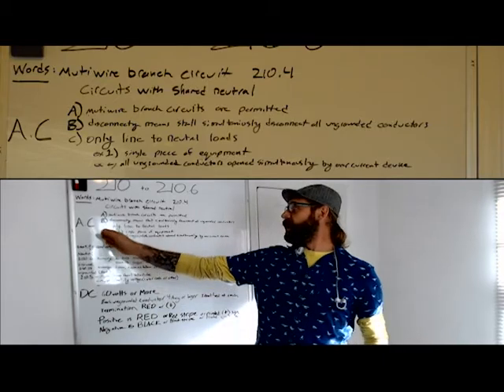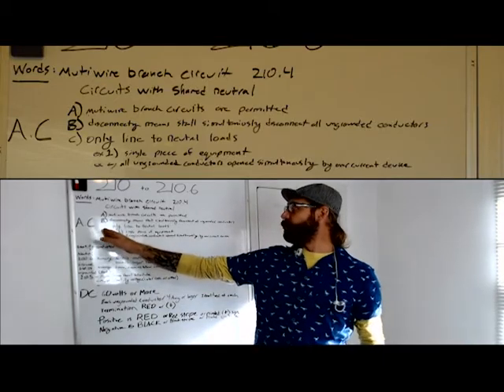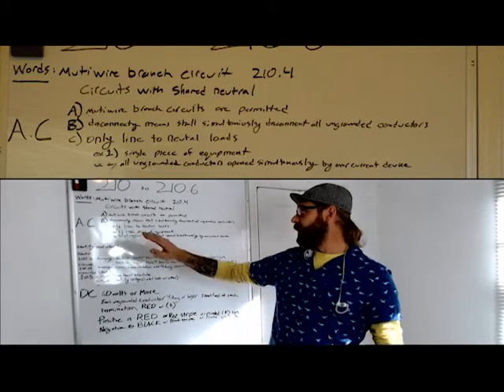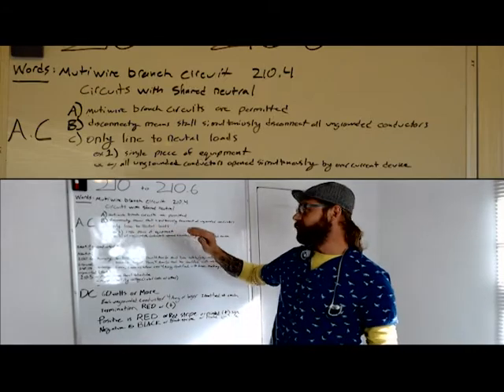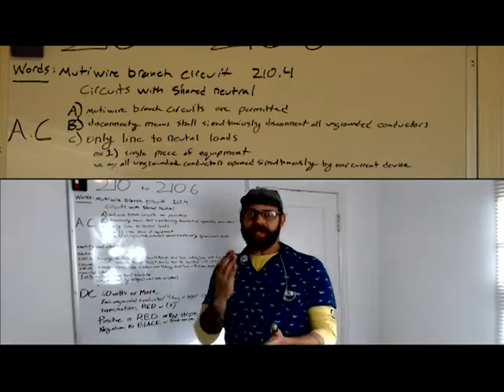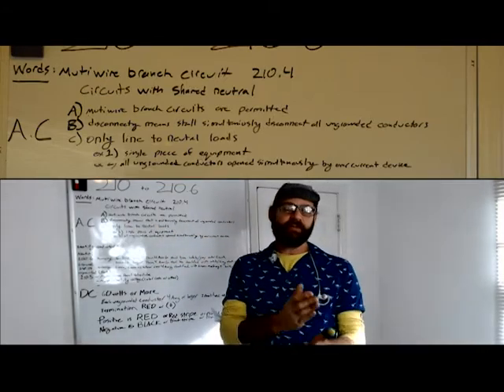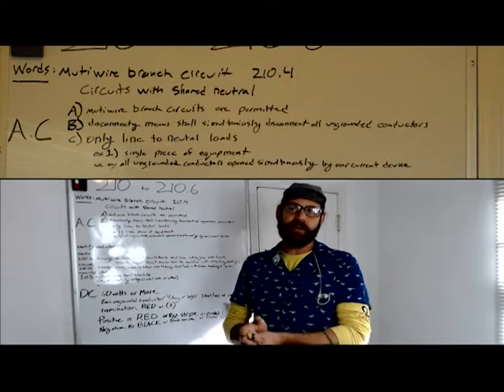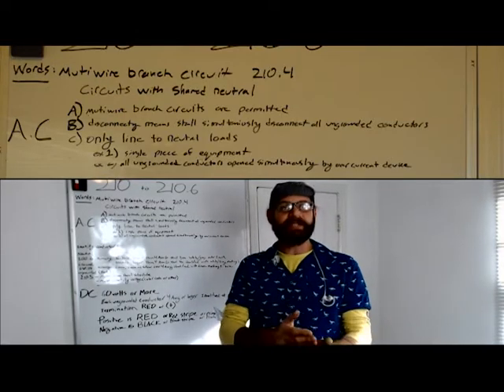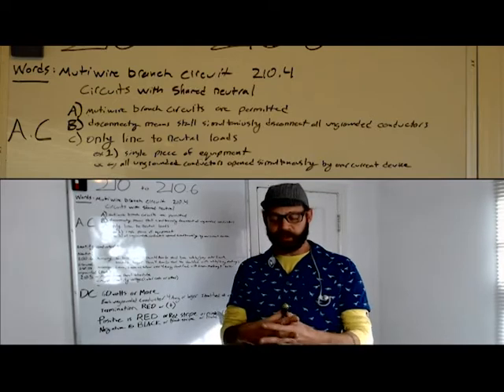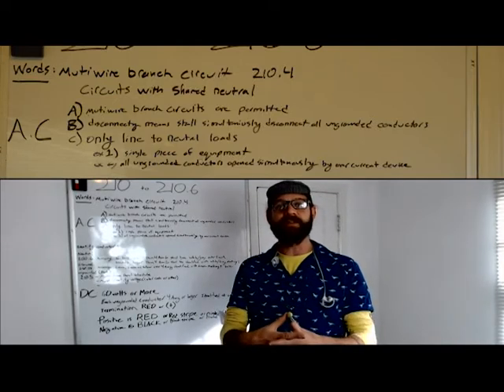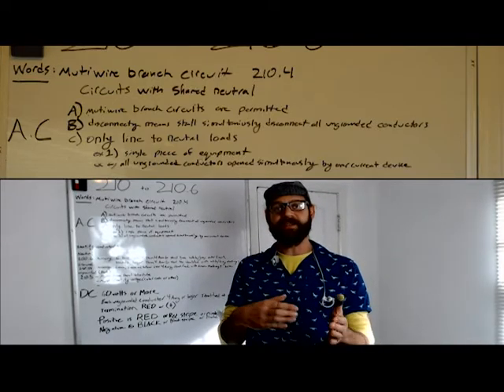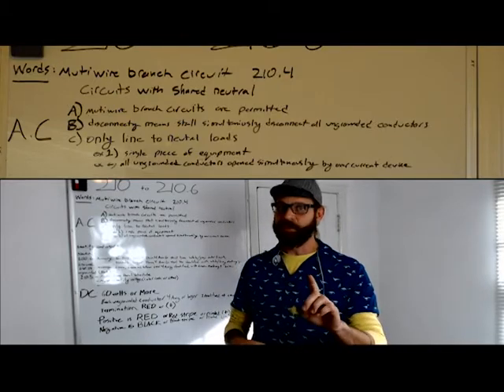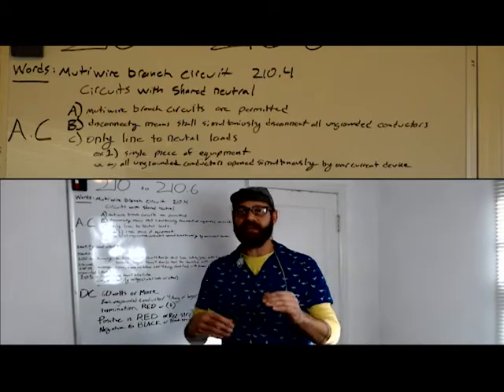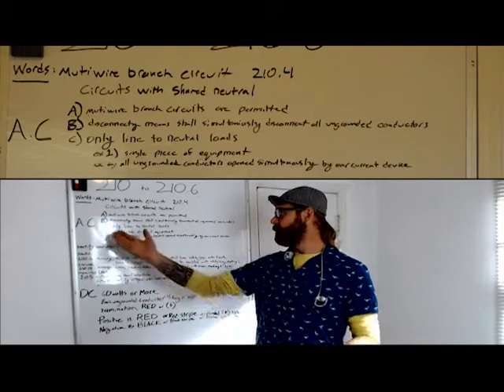210.4(C) says it shall only supply line to neutral loads. That is, in a 120/208 system, the multi-wire branch circuit is only going to supply the 120 volt loads. It won't supply the 208 volt loads. There are 2 exceptions though, and I think these 2 exceptions actually overrule the entire (C).